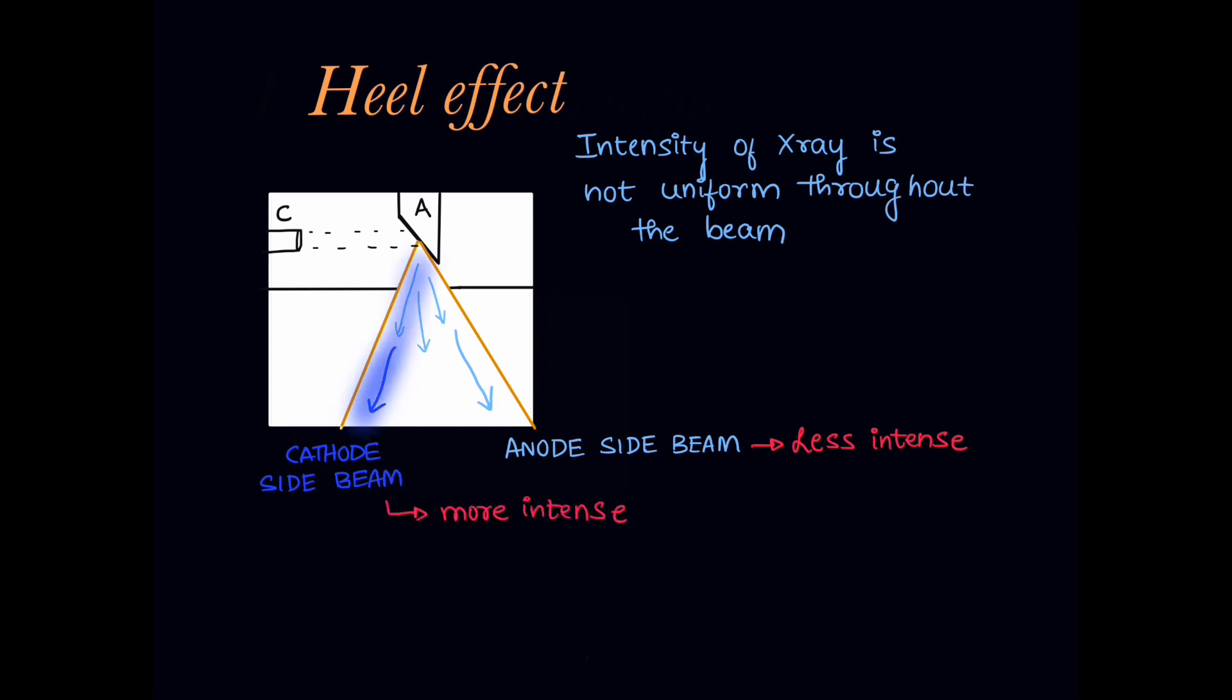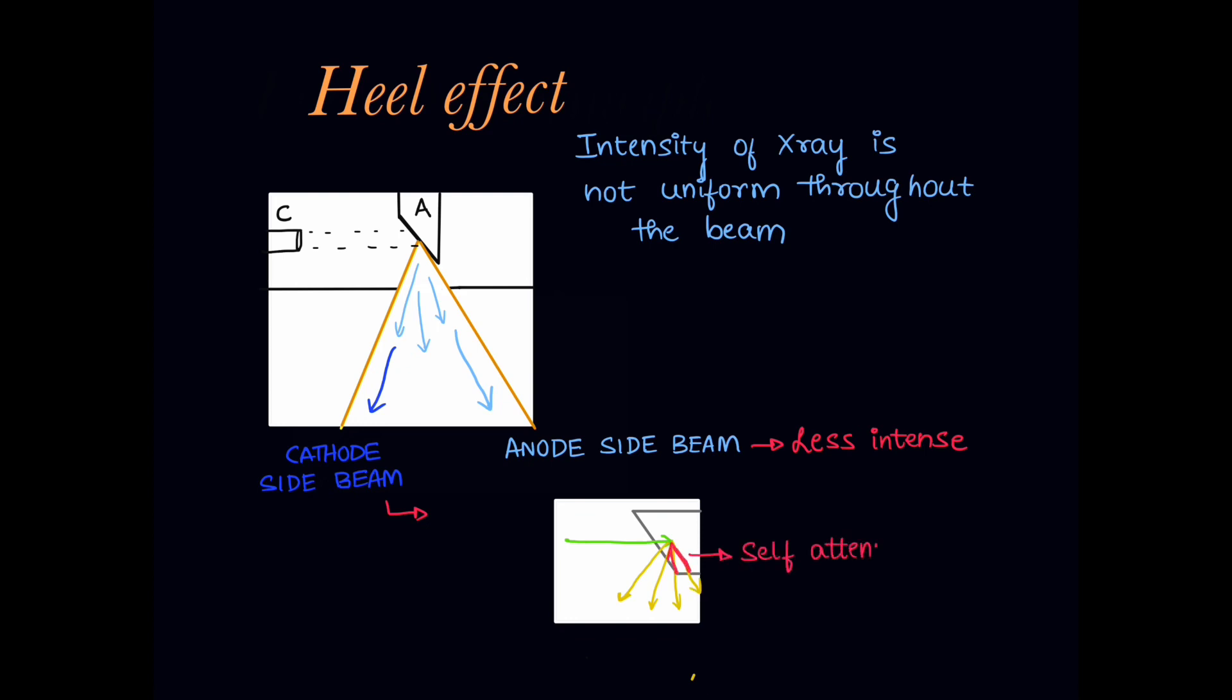The strength or quality of the x-ray beam produced will look something like this, more intense towards cathode side and less intense towards anode side. The reason for this being self-attenuation of the primary x-ray beam produced by the anode itself that makes it less intense towards anode side and more intense towards the cathode side.